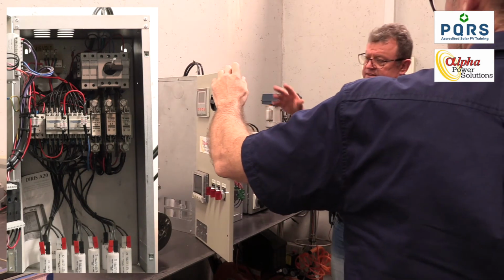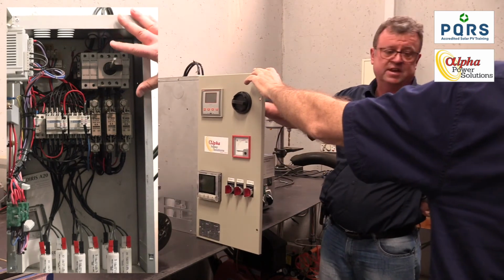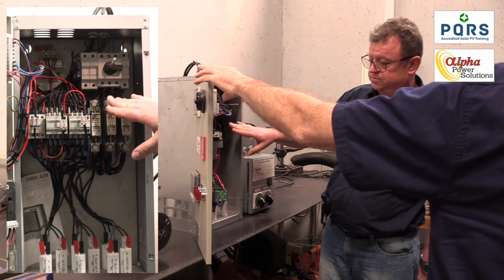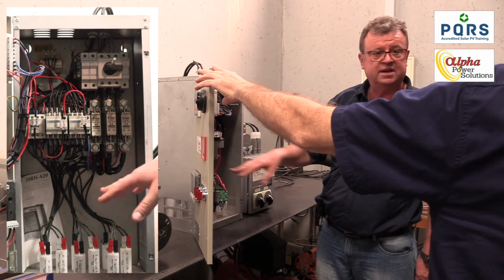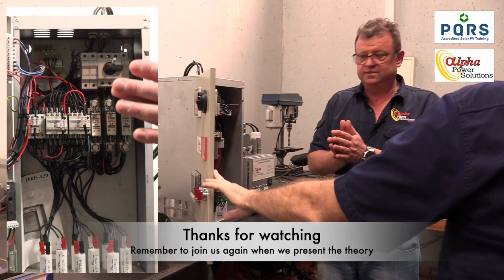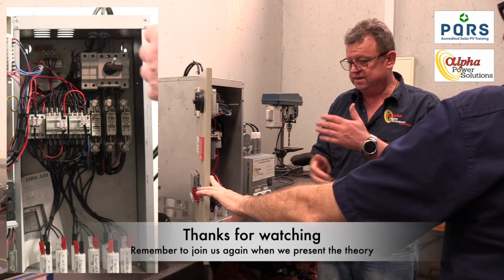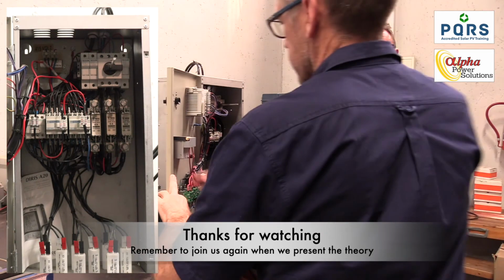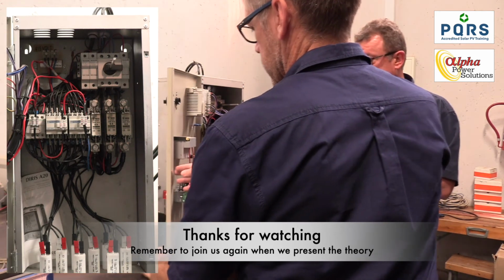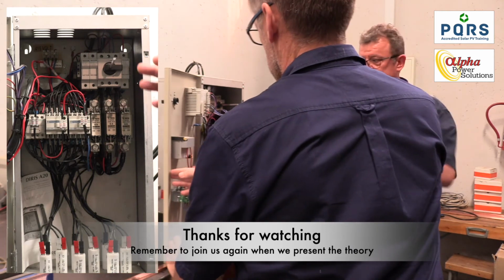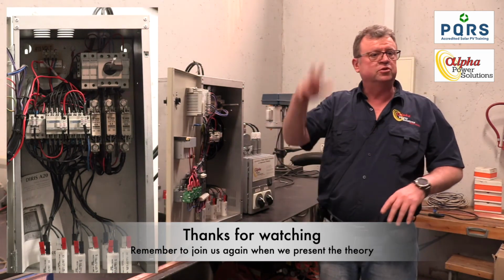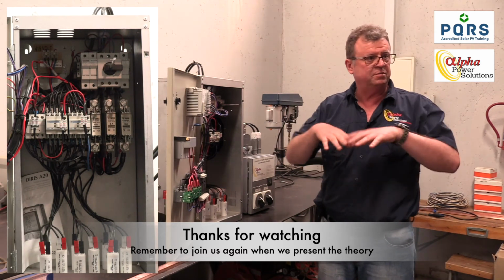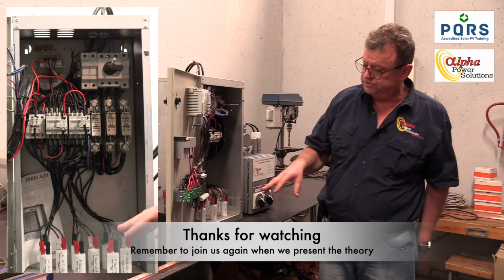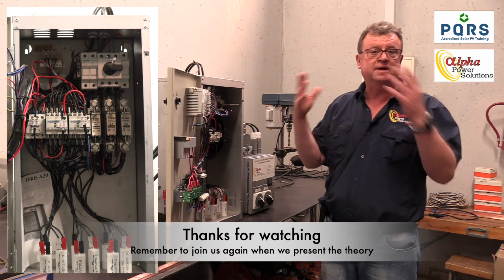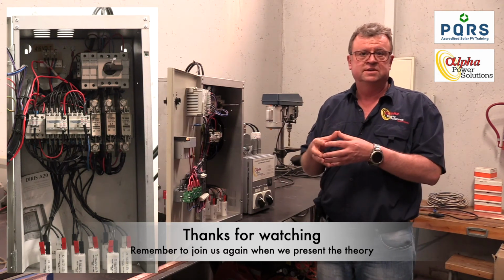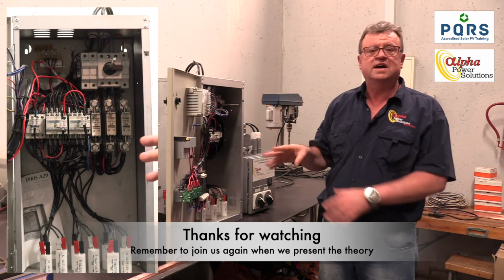So basically, the key components are: you've got an isolator, you have to have an isolator. You have fuses to protect the system. You have contactors to energize the capacitors. The total reactive compensation is broken up in blocks, so that the system can bring in capacitors as required. As the load changes, in a factory rather than just a motor, you'll have motors starting and stopping, so the reactive power usage of a plant is never stable. So you break the total amount of kilovars needed by the plant up in blocks, and you tell the brain what the size of these blocks are.